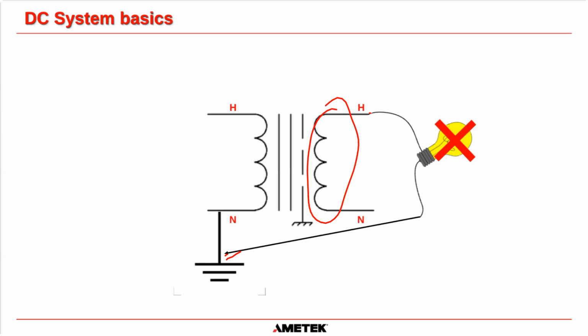I say it in my training class when I'm training new UPS technicians here at the Stafford office. If you wanted to, and I don't recommend anybody ever do this, but as an example, somebody could put their hand on this ground or earth bar here, and then put their other hand on this hot connection here. Obviously, you have to measure to make sure there's no potential, and you will not get an electric shock. There is no path for the current to flow. All you're doing at that point is making hot the same reference point as ground using the resistance of your body. No current will flow.